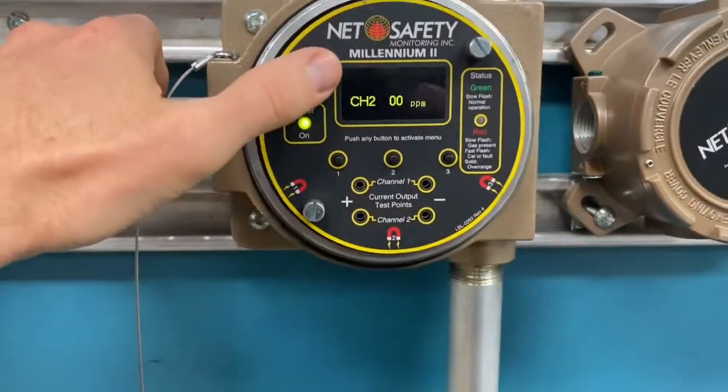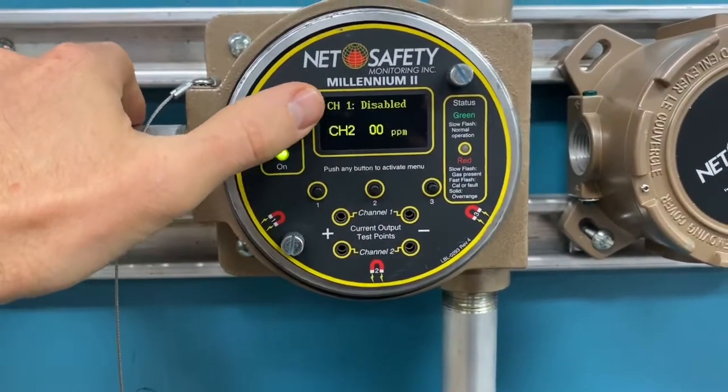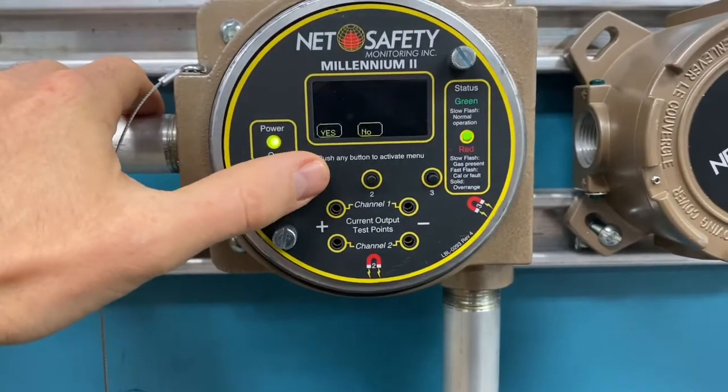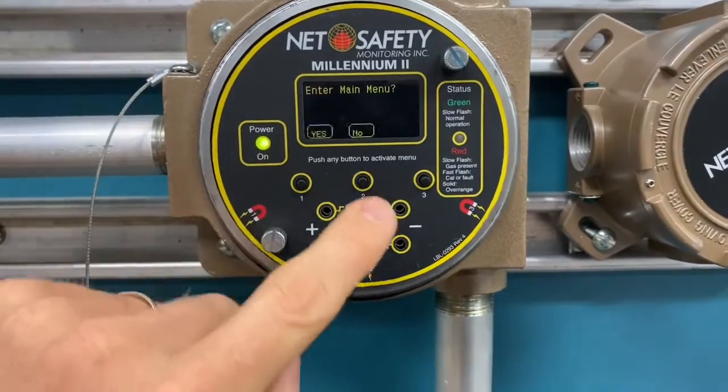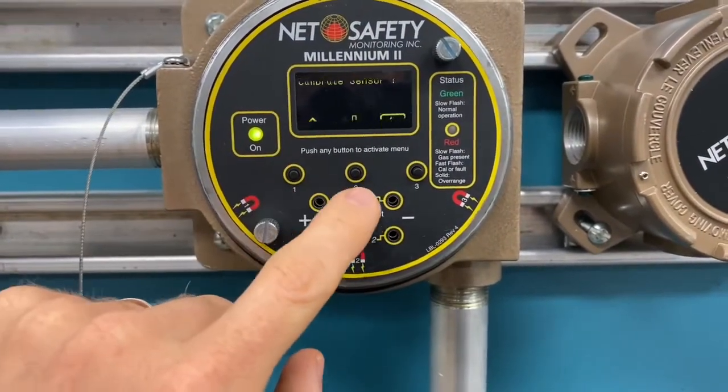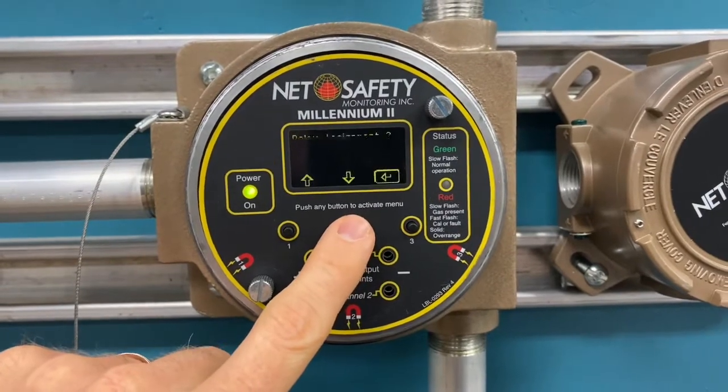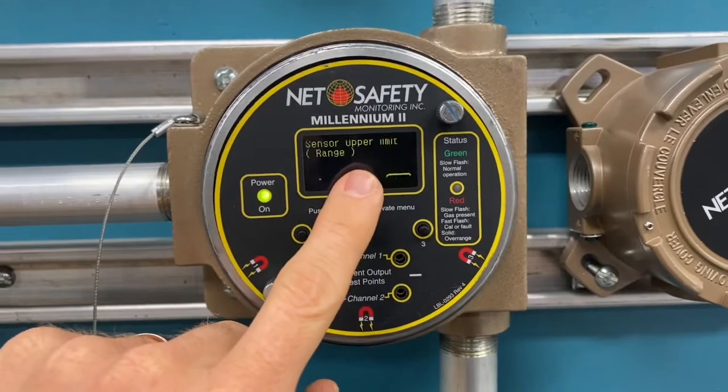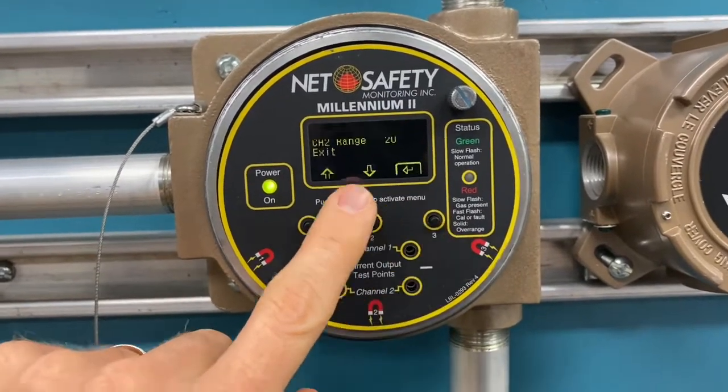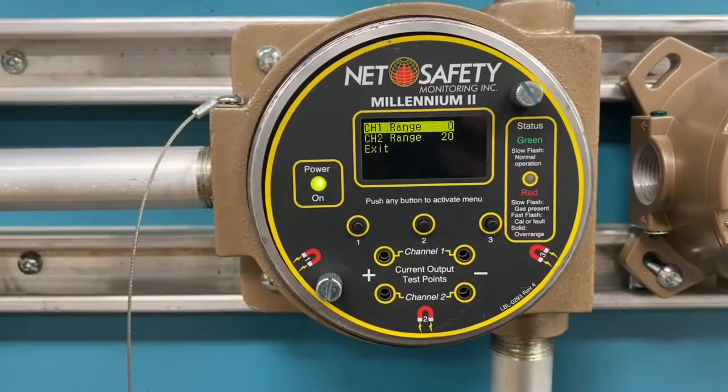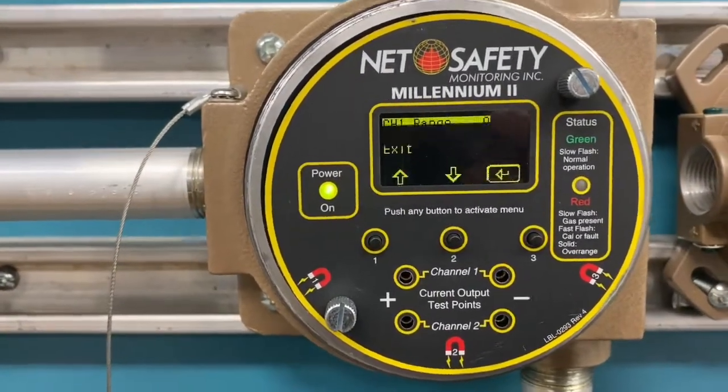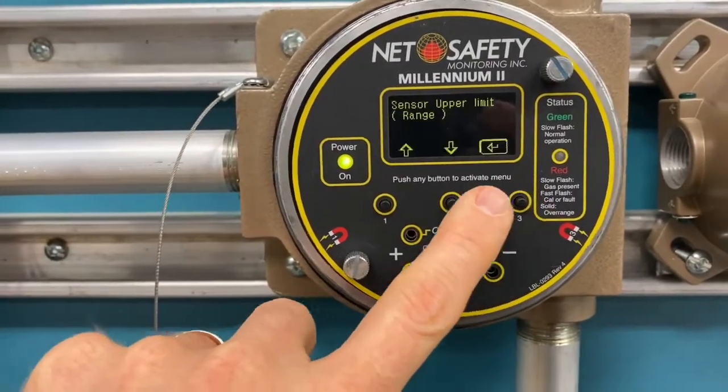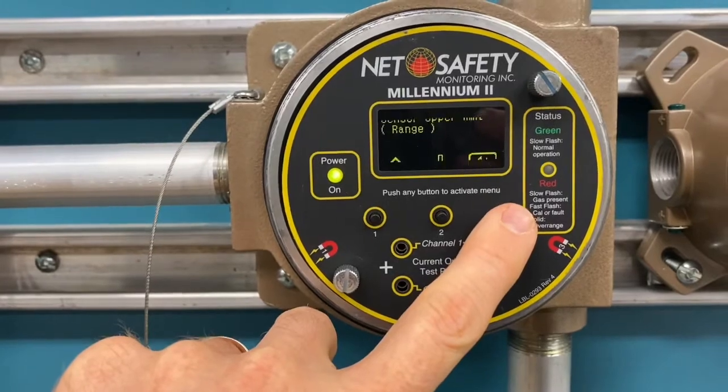The lab says we want to have channel one disabled and channel two enabled. You can see that's the way it's set up right now. One other thing we want to check is we want to make sure the range is set correctly. I push button one, enter the main menu, click one again to say yes. Now we're going to scroll down. The sensor upper limit or range needs to be set for 20, because that's what our sensor is configured for, 20 PPM. Now I'm just going to exit. We're going to perform a calibration.